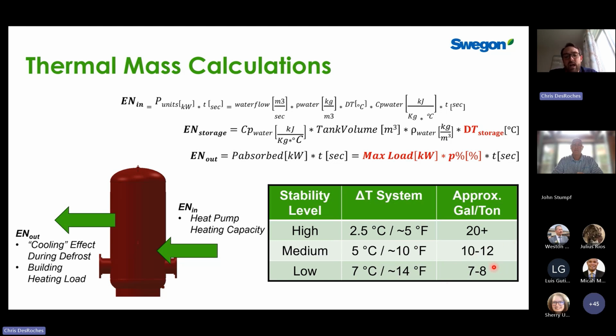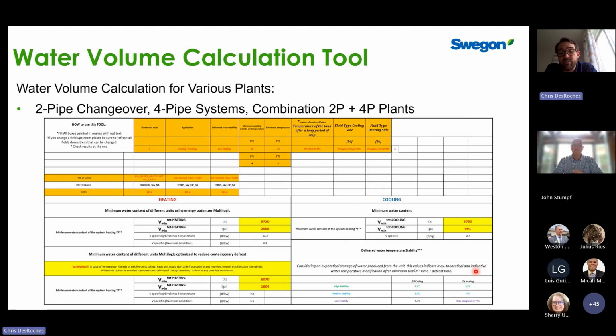So a lot of times we'll do a sizing calculation for a customer. We'll provide a calculation for low stability and medium stability, and oftentimes engineers pick something somewhere in between. So that's just the physics of it. It's not unique to Swegon. It's just net heating and cooling capacity for the duration of defrost and what temperature change that will influence.